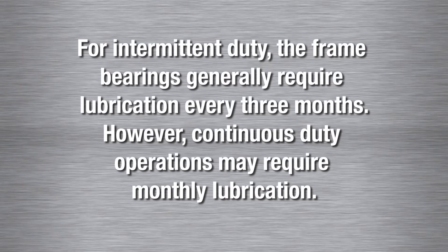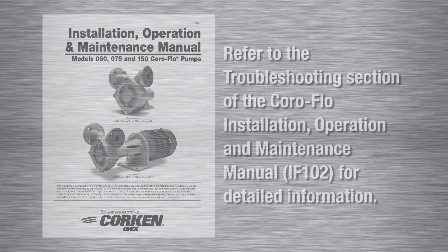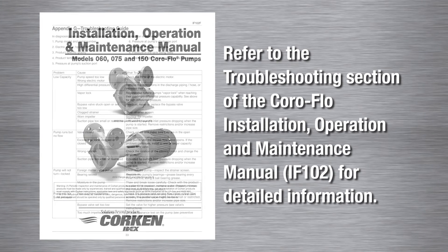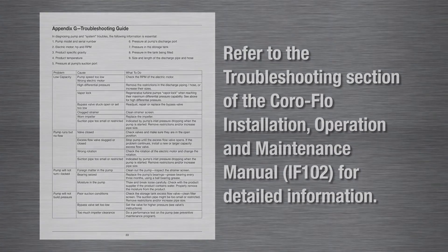However, continuous duty operations may require monthly lubrication. Corken recommends only using military grade 10924C ball bearing grease with a temperature rating of minus 50 degrees Fahrenheit. Please refer to the troubleshooting section of the Coro-Flo Installation, Operation, and Maintenance Manual item number IF-102 for detailed information. This manual may be downloaded from the literature section of our website at corken.com.